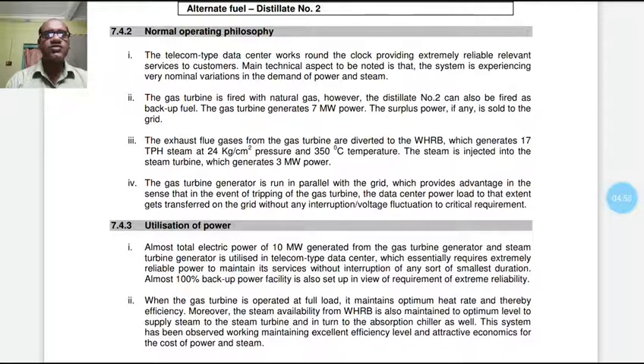The exhaust flue gases from the gas turbine are diverted to the waste heat recovery boiler, which generates 17 TPH steam at 24 bar pressure and 350 degree centigrade temperature. The steam is injected into the steam turbine, which generates 3 megawatt power. The gas turbine generator is run in parallel with the grid, which provides the advantage that in the event of tripping of the gas turbine, the data center power load to that extent gets transferred to the grid without any interruption or voltage fluctuation to critical requirements.